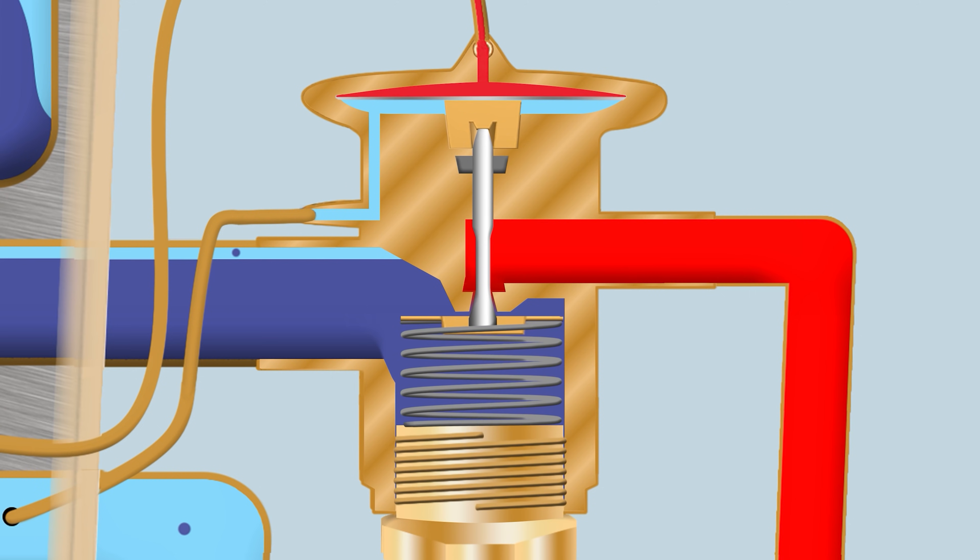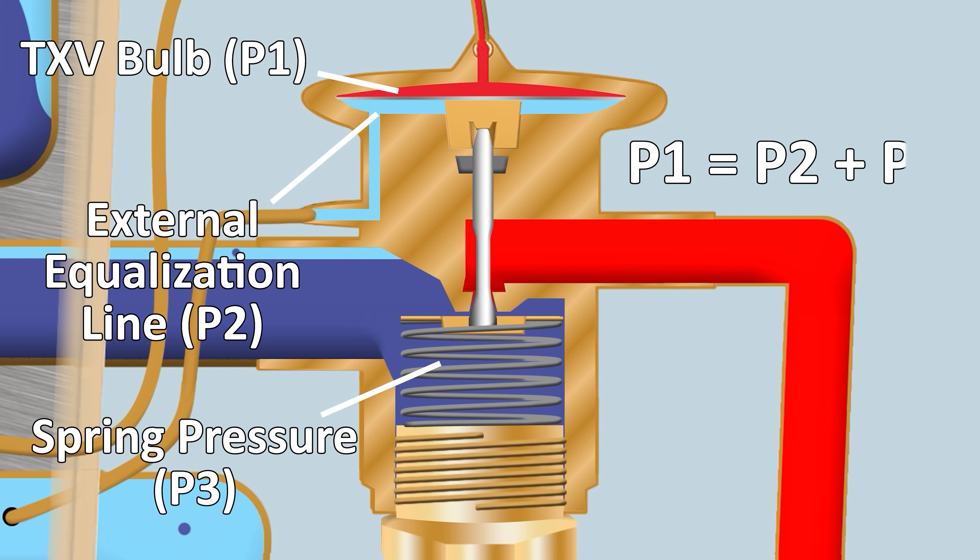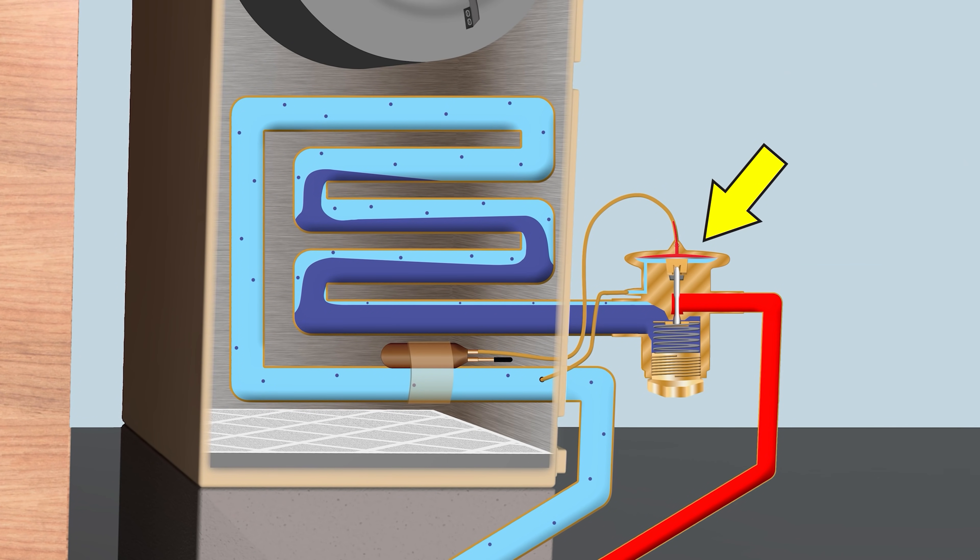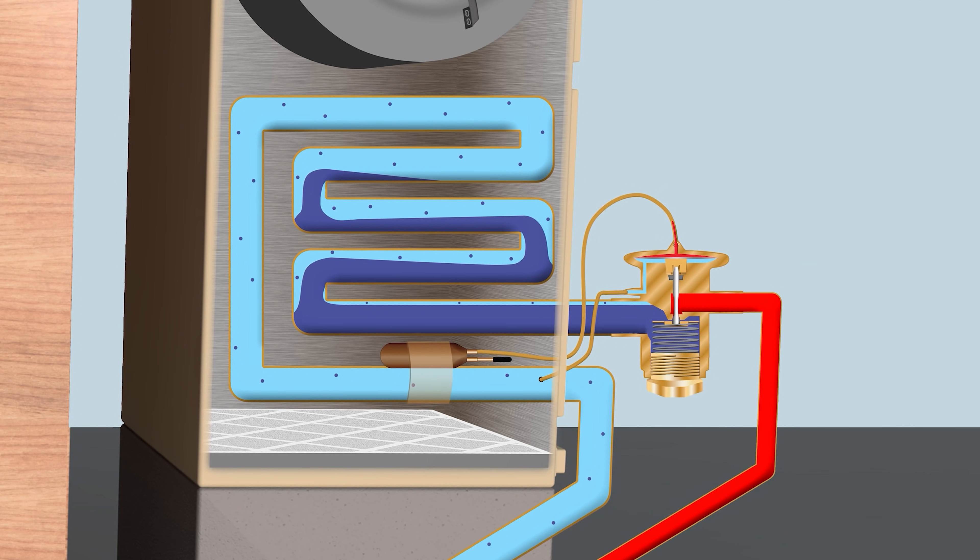What you need to know about the TXV is it's able to hold this little opening in equilibrium and increase or decrease the size of that opening. It uses P1 equals P2 plus P3, so it uses that formula in order to hold that opening in equilibrium, and what this TXV is really doing is maintaining its superheat.